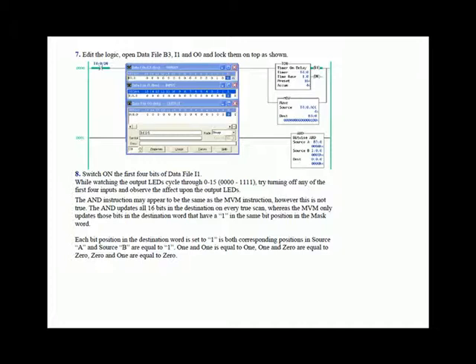Whereas the mask move only updated those bits in the destination that were open through the mask — if in that bit position in the mask there was a 1, it would update that position from the source. The bitwise AND updates the destination every single true scan. Each bit position in the destination is set to 1 if both corresponding positions in source A and source B are equal to 1. 1 and 1 equals 1. 1 and 0 equals 0. 0 and 1 equals 0. Very simple instruction.